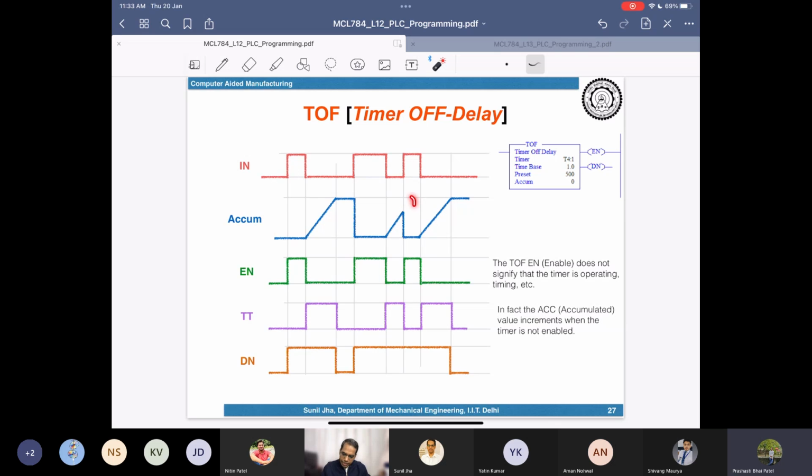So in this second case, you take out the key and you want to go out of the room, and then, before the delay that has been programmed has lapsed, you realize that you want to go back inside the room and search for something, so you place the key back. Then the room lights will not go off. They will remain on because we have not waited for that delay time. And that is how it has been reset at this point of time. And again, this will be ready to take up the timer input again next time.